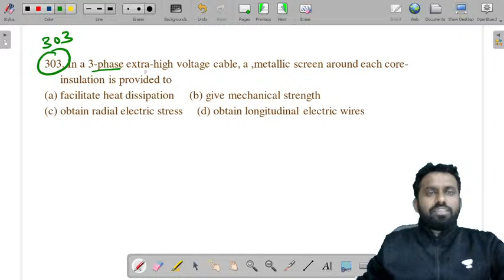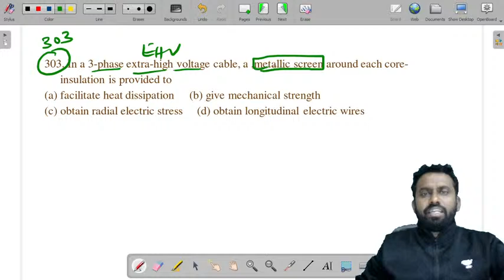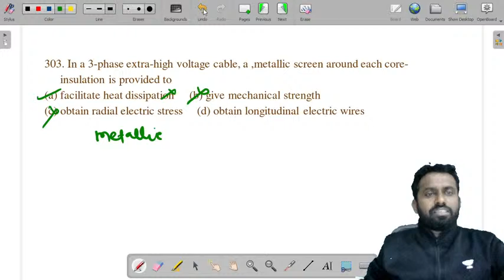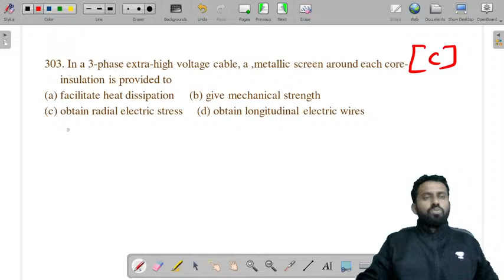Now question 303: In a three-phase extra high voltage (EHV) cable, a metallic screen or metallic paper around each core insulation is provided to do what? Is it to facilitate heat dissipation? No. To give mechanical strength? No. To obtain radial electrical stress? Yes. To obtain longitudinal electrical waves? No. So the metallic paper around each core insulation is provided to obtain radial electric stress. The answer to 303 is C.